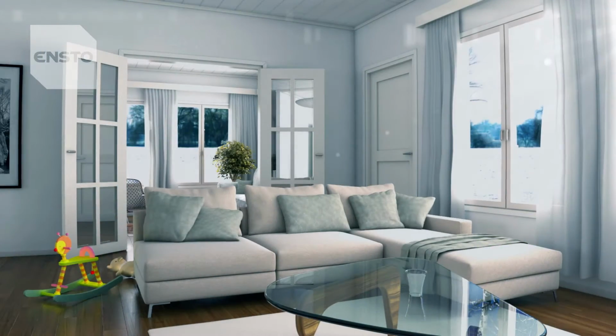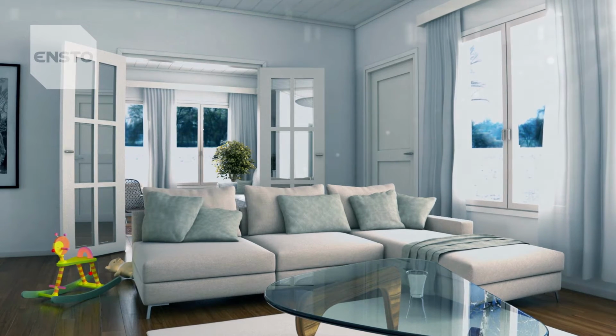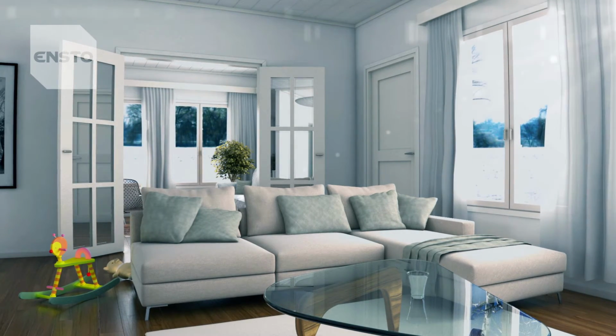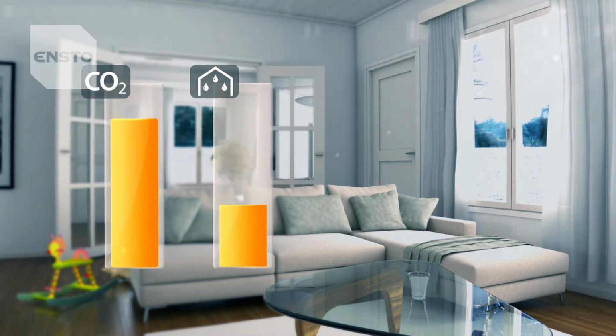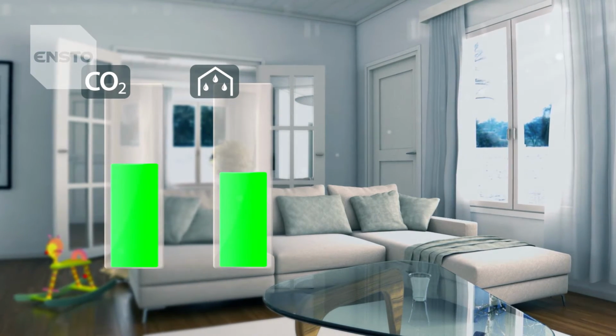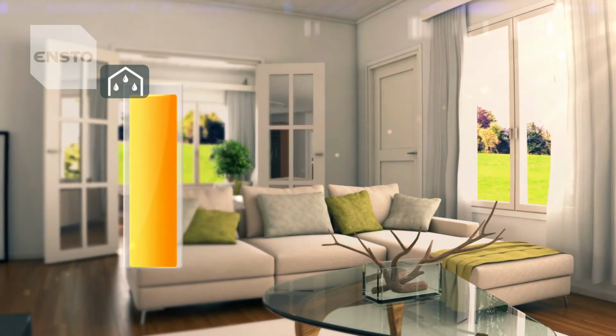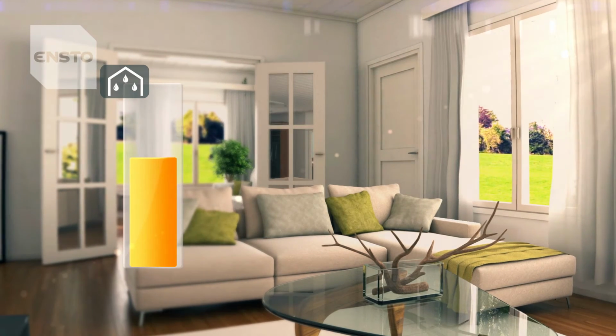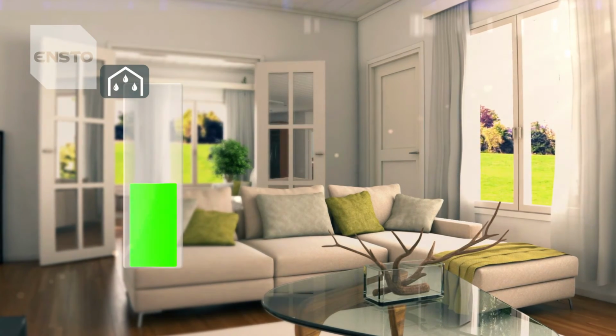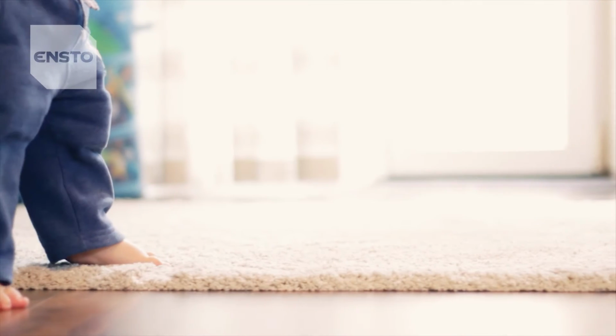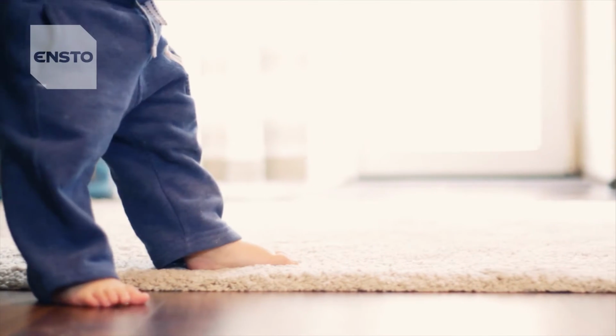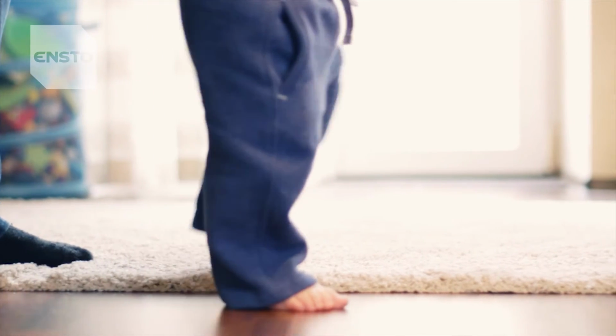The mechanical ventilation can be used to manage the freshness and temperature of the air, but also other factors of indoor air, such as humidity and carbon dioxide levels. Any extra humidity that could otherwise end up in the structures and cause moisture damage is removed from the building in a controlled manner. Therefore, mechanical ventilation is important for the building, and it helps to maintain the property's value in the future.